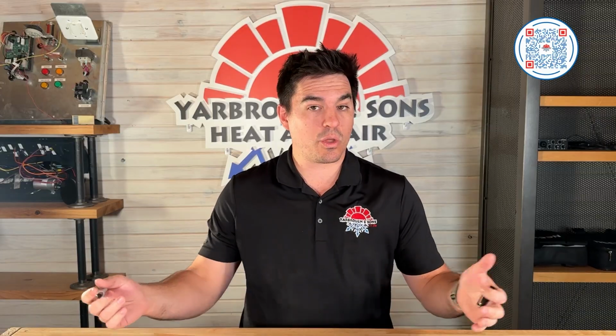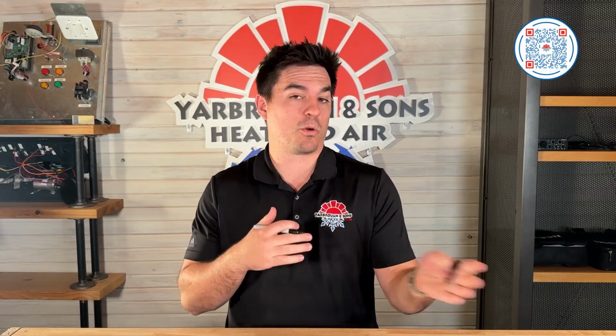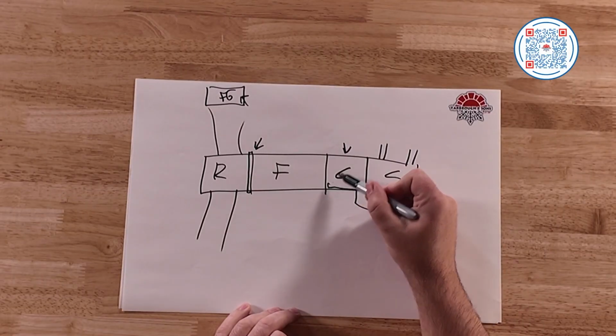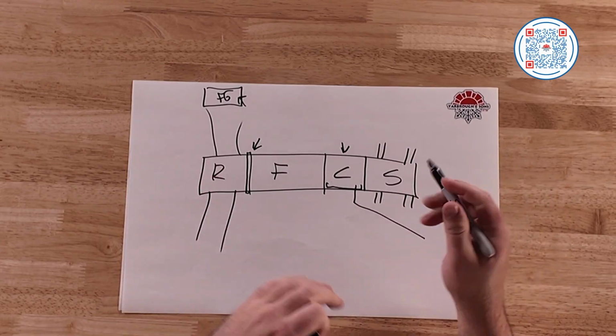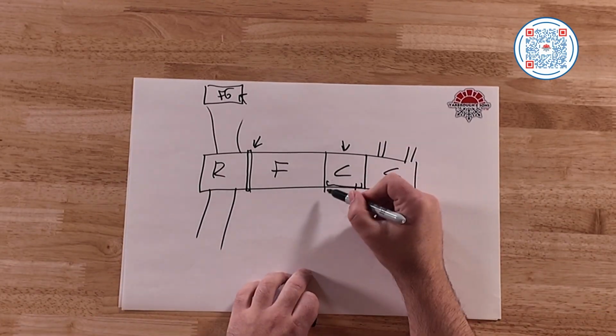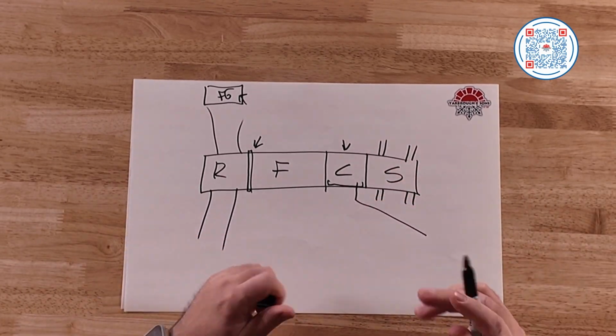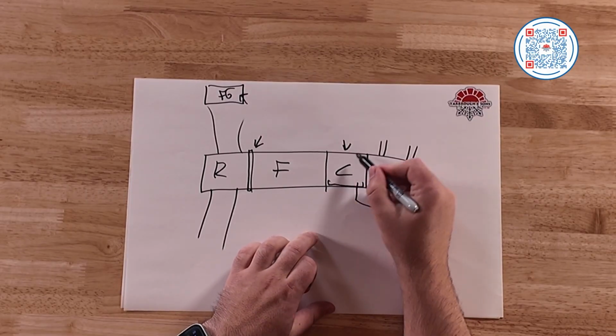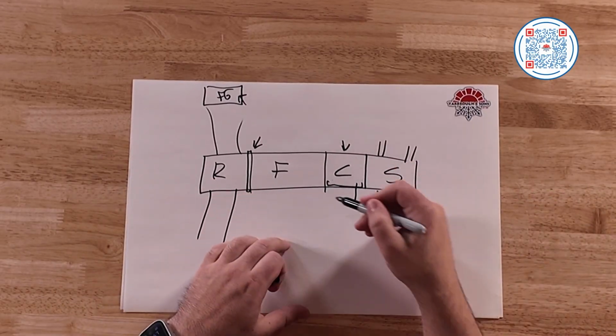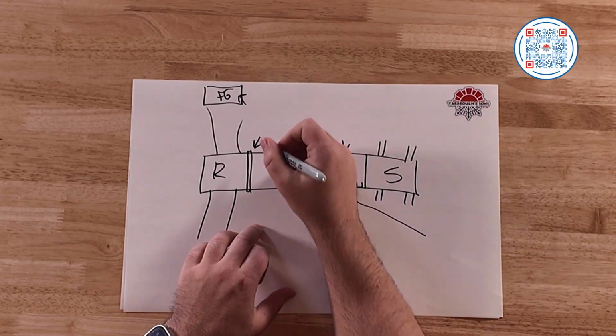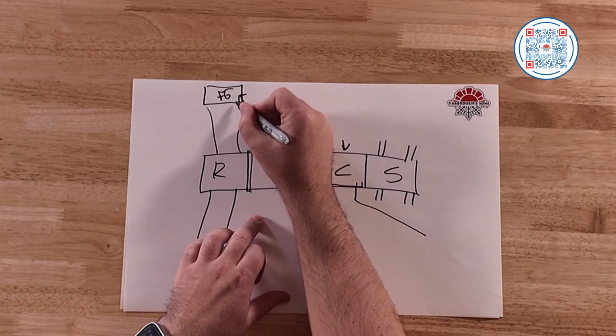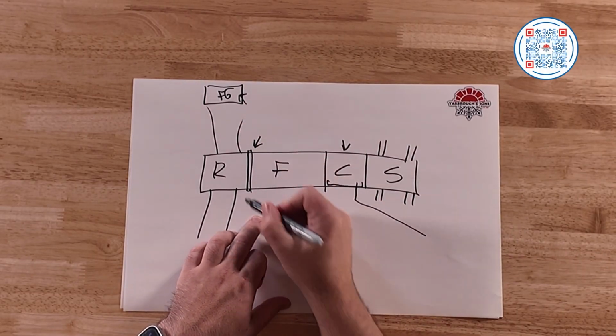And these newer units remove more humidity from the house, which means you're going to have an excess of water in the evaporator coil, which is great for the living environment, bad for this environment. So you want to make sure, one, that this is completely clean. You're not getting an excess of debris and contaminants on the evaporator coil. Double check and make sure your filters are changed, either at the filter grill or before the unit.